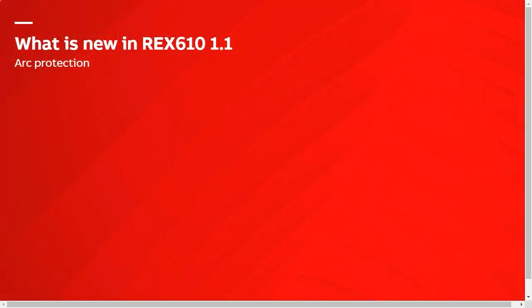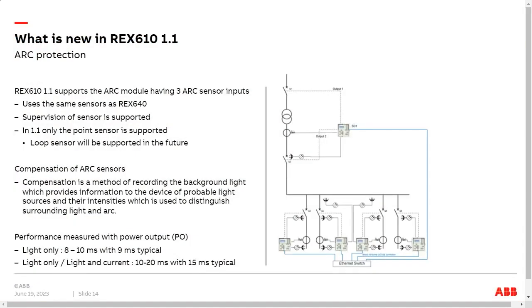Okay, I promised that we need to take a little bit of a look at the ARC protection function, because there's at least one new function block there, this ARC function block. So if we start with the basics, the REX610 1.1 firmware supports the ARC module having 3 ARC sensor inputs. It uses the same sensors, if you're familiar with the REX640.